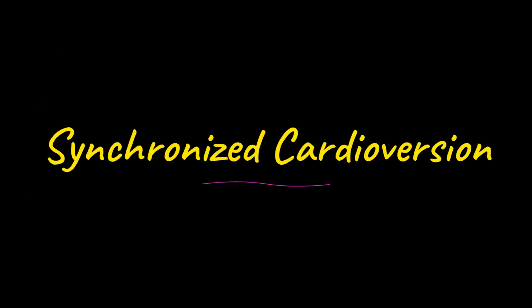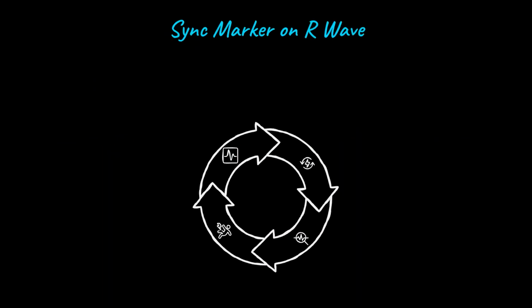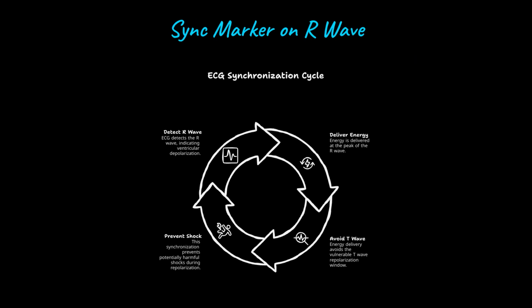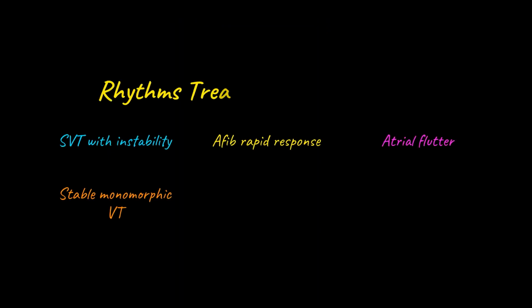Synchronized cardioversion is a timed electrical shock used to convert a fast, organized arrhythmia back to normal sinus rhythm. The key word is synchronized. The device times its energy delivery to coincide with a specific moment in the cardiac cycle. The device fires on the R wave, not randomly, because delivering energy during the T wave would hit the vulnerable phase of repolarization, which can trigger ventricular fibrillation. Syncing to the R wave makes the shock safe and effective.